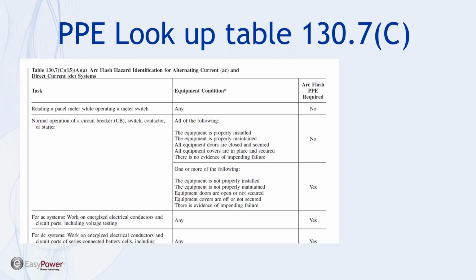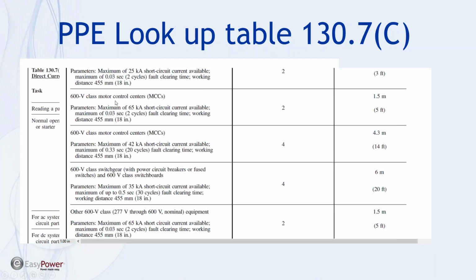According to 130.7(C), if we start from the top of the table and look down here at AC systems, if we're going to work on energized electrical conductors and circuit parts, including voltage testing, then we need to have PPE. All right, so that's the first step in determining PPE. We slide farther down in the table and we find, if we're looking at 600 volt class switchgear with power circuit breakers or fuse switches and a maximum of 35,000 amps short circuit current with a maximum of half a second fault clearing time, then the requirement is to use PPE 4 from these categories.